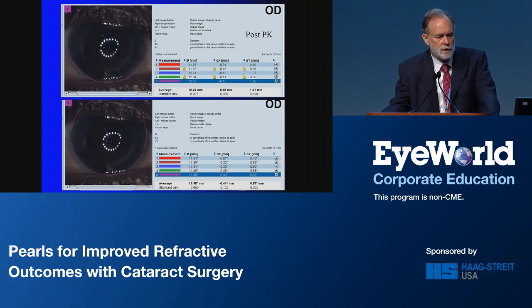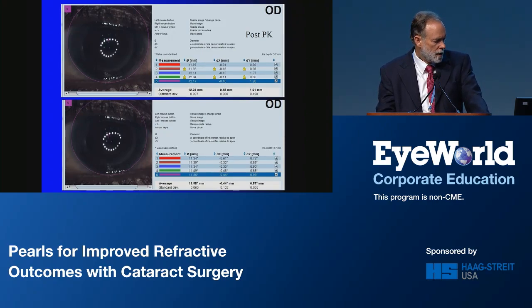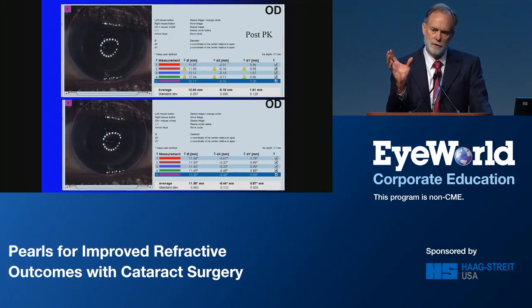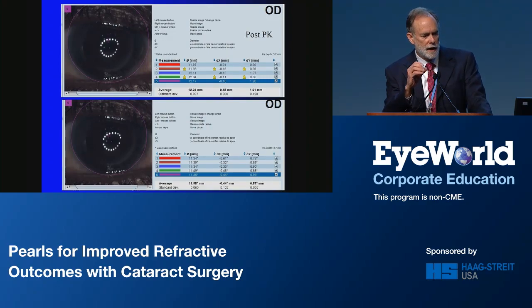What it is, if you look at the purple line that outlines the limbus on the left side, you can see that it's offset a little bit, and it's out over onto the sclera or the limbus a little bit more than it should. So what my technician did was they made the circle for the limbus smaller, and they moved it a little bit over the center to the left and downward.